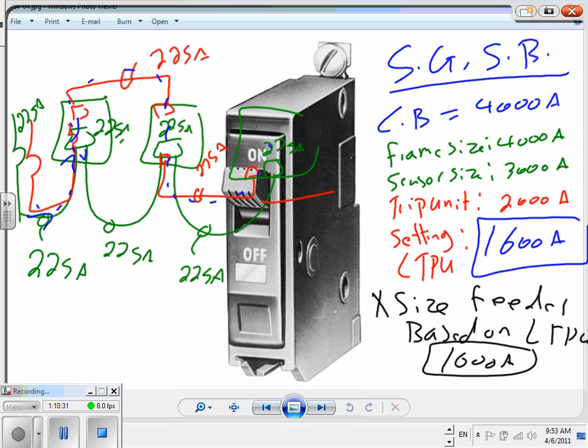Why would anybody do something like that? In the future, I can change the sensor here to 4,000 amp, change the trip unit to a 4,000 amp, and change the setting to 1, which will give me 4,000 amp. The same circuit breaker becomes a 4,000 amp circuit breaker. It probably will take you, shut down, about 20 minutes to do all these changes, especially the sensor, where you need to shut down. The plug-in, guys, see that trip plug-in?